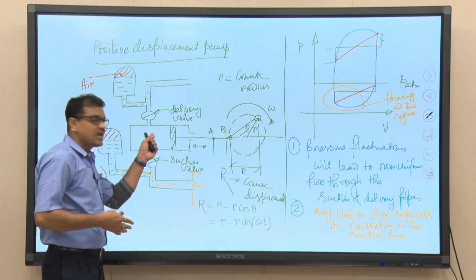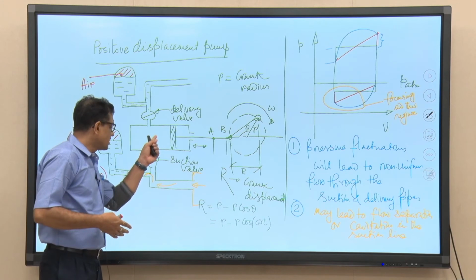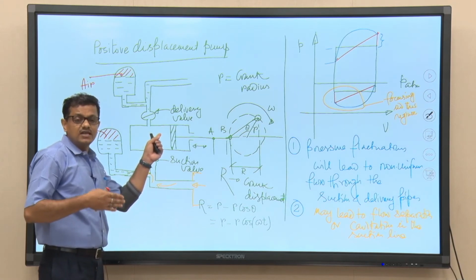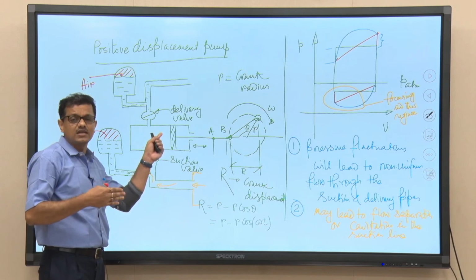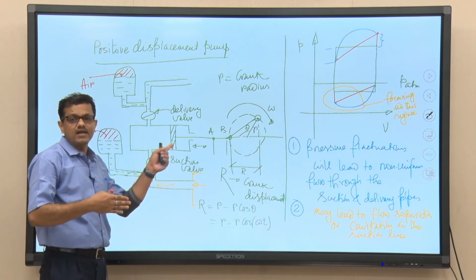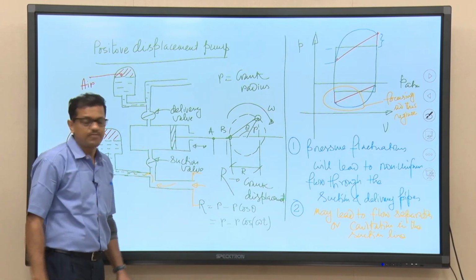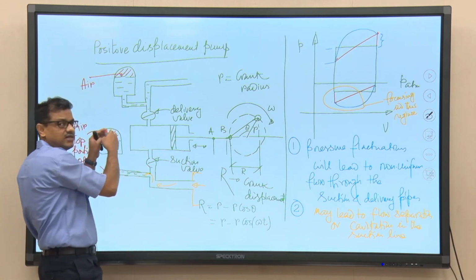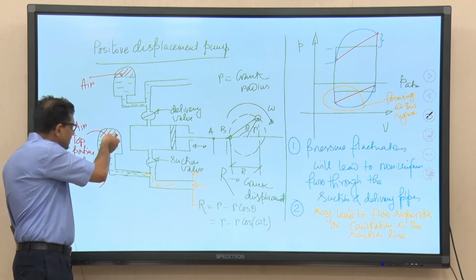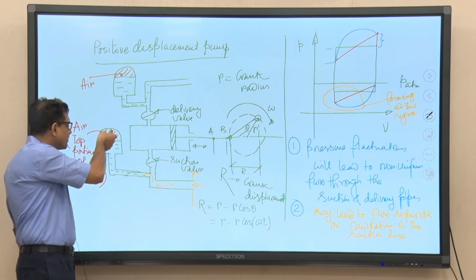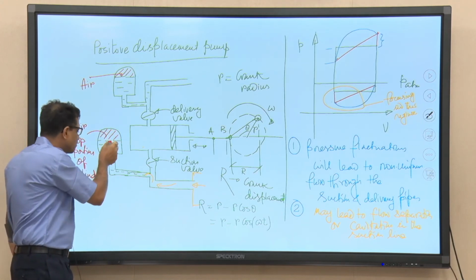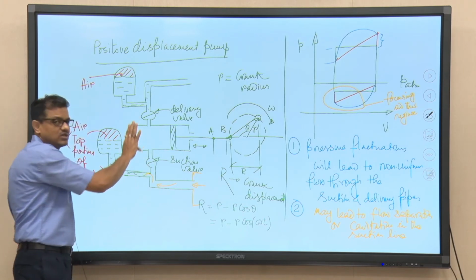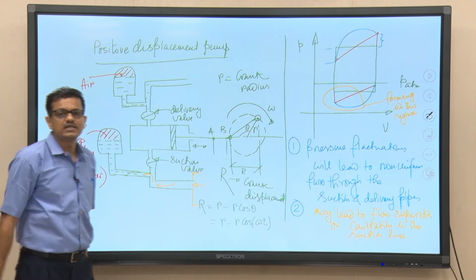Though the pressure difference has reduced, that reduction will not have any impact on the flow rate. The energy remaining stored in the compressed air will allow the liquid to move from the air chamber through this line into the cylinder. So, the pressure fluctuation can be avoided.